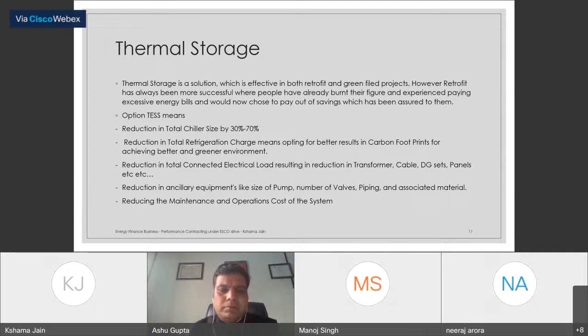With thermal storage, we see a reduction in the total size of the chiller, about 30 to 70%, and a reduction in total refrigerant charge, giving better results on carbon footprint for a greener environment. There's also a reduction in connected electrical load, which reduces transformer, cable, DG set, and panel requirements, plus a reduction in ancillary equipment like pumps, number of valves, and piping, reducing the maintenance and operating cost of the system.